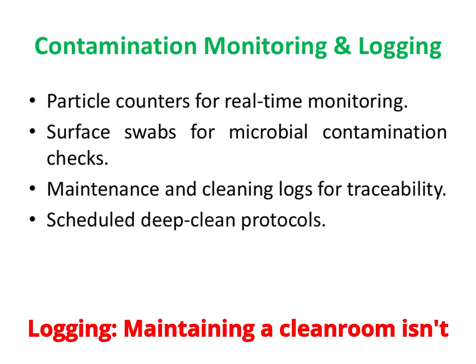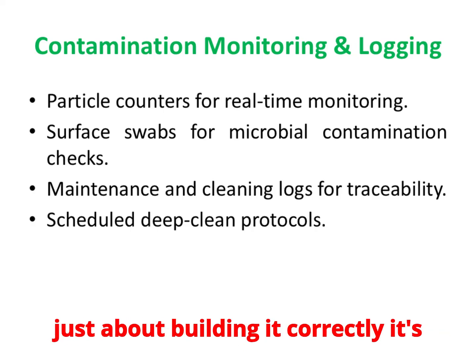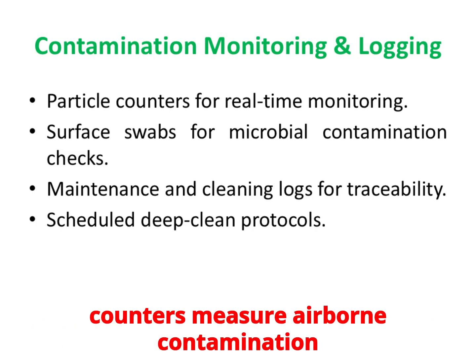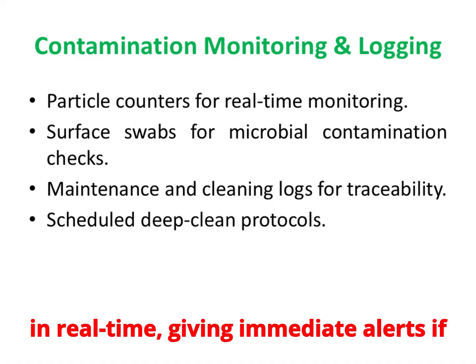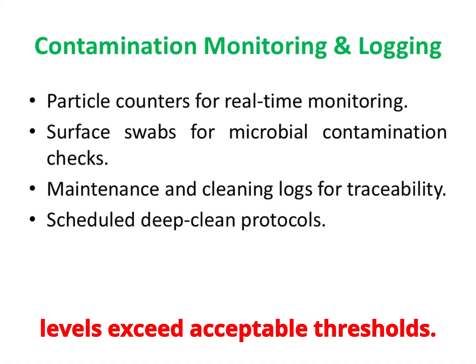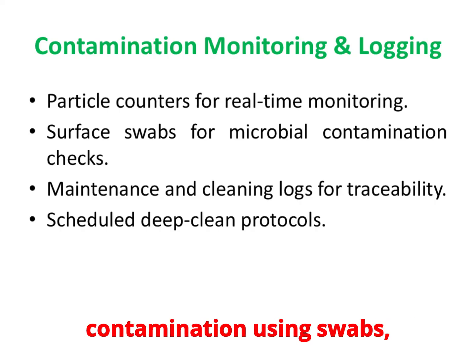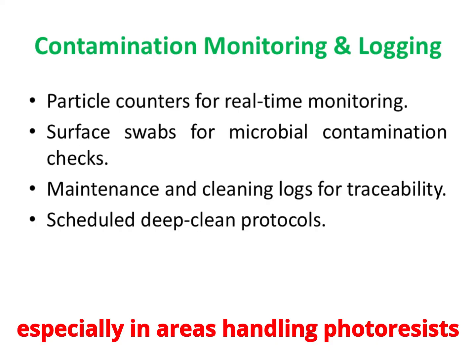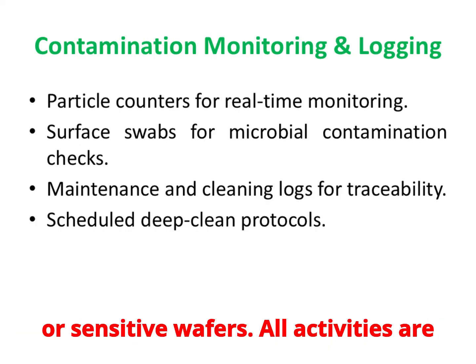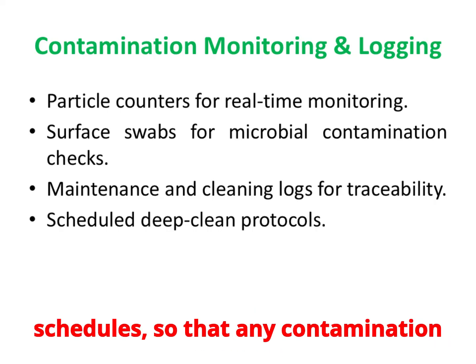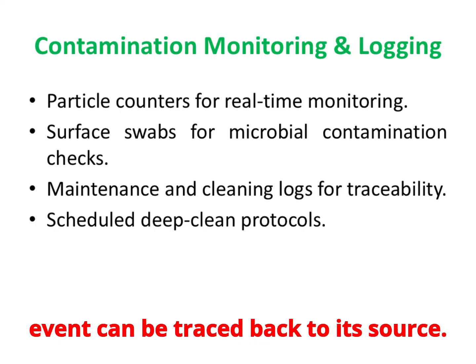Maintaining a clean room isn't just about building it correctly — it's about continuous monitoring. Particle counters measure airborne contamination in real time, giving immediate alerts if levels exceed acceptable thresholds. Surfaces are tested for microbial contamination using swabs, especially in areas handling photoresists or sensitive wafers. All activities are logged, from maintenance work to cleaning schedules, so that any contamination event can be traced back to its source.